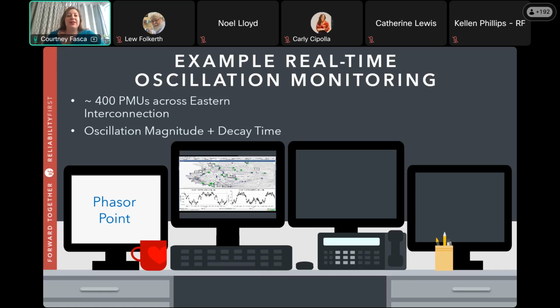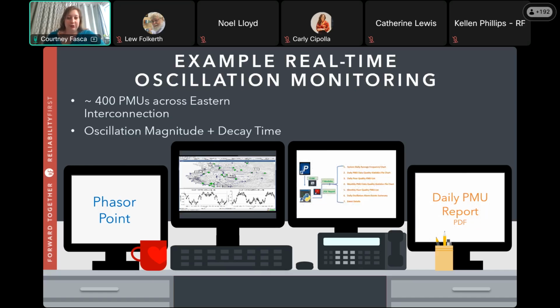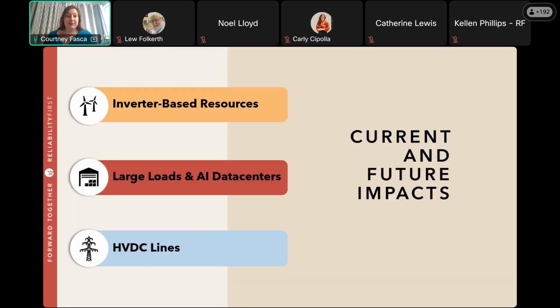So in order to enhance the situational awareness for the control rooms, this company automatically generates a PDF file of the daily PMU report, which is then archived in an internal shared folder. That report includes information on the system average frequency, summaries of oscillation events, detailed event charts, and PMU data quality statistics, and it actually even lists the poor quality PMUs that are in need of maintenance.